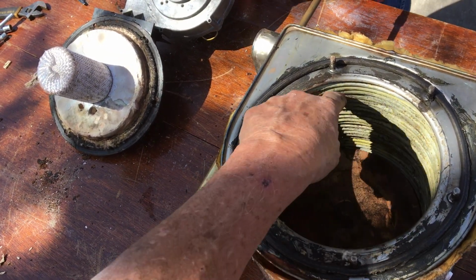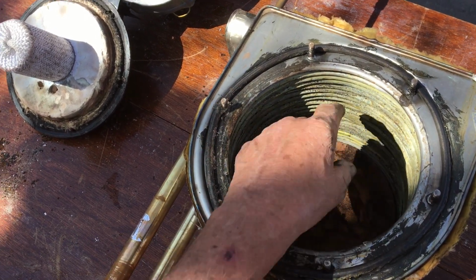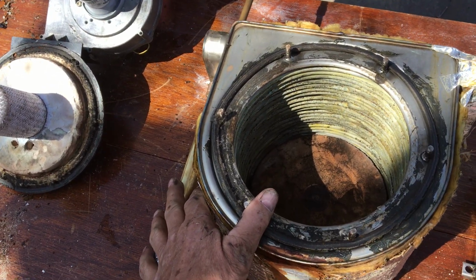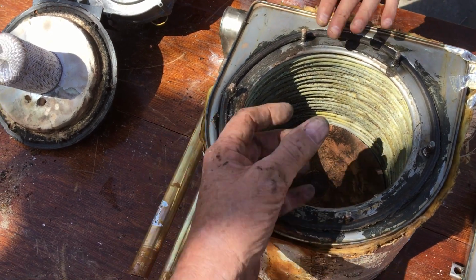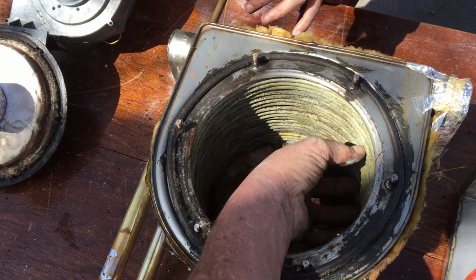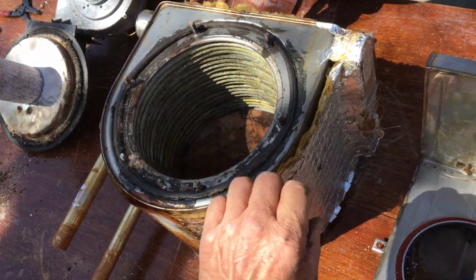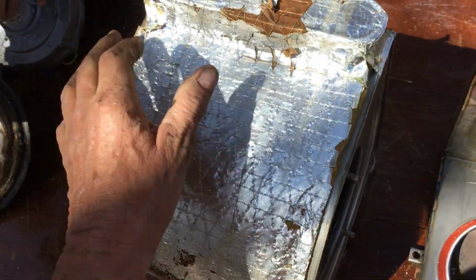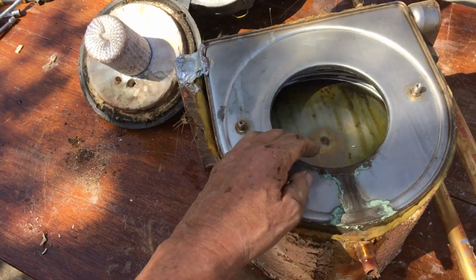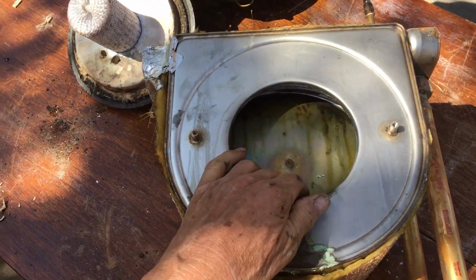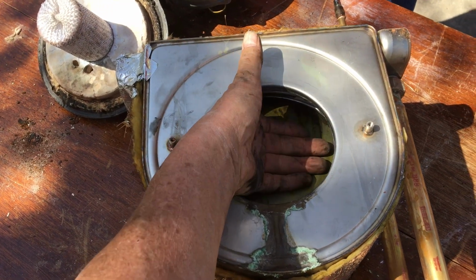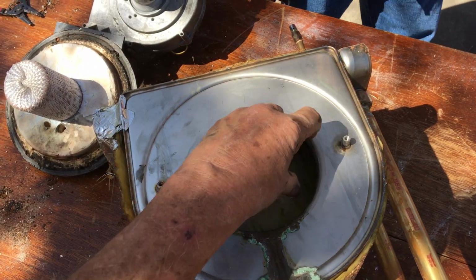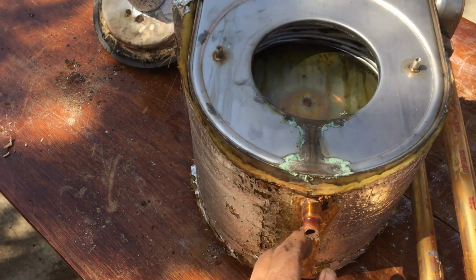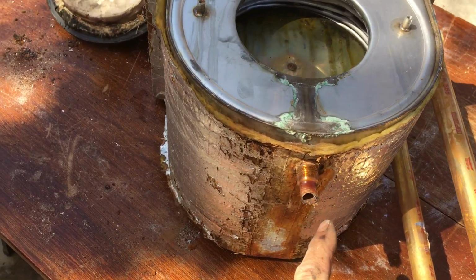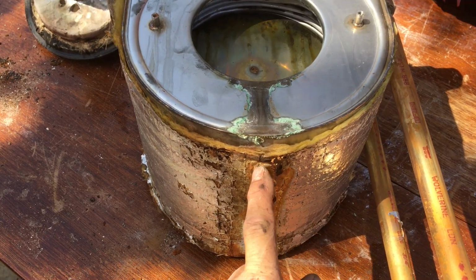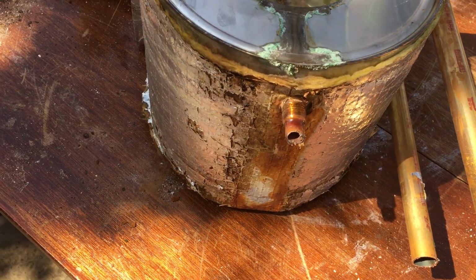You can see the heat exchanger is just these spiral stainless steel tubes that go around. What happens is the flue gases go between the tubes into this outer jacket, and then re-enter the secondary chamber, where much of the condensation takes place. So we have a condensate drain here.